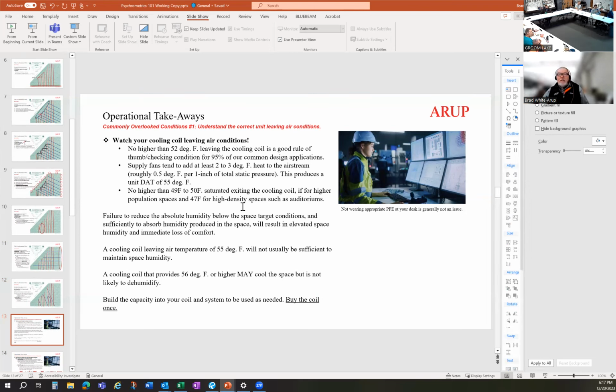What I also find is that if you're doing a performing arts center or a museum or a conference center where you've got a lot of people in one space, you have to get that air a lot colder. You probably have to get it down below 47, sometimes below 45, to get the moisture out of that air. Costs a lot of money. It's kind of expensive to go chasing humidity, but the energy cost is worth it if that gives you what the space requirements are.